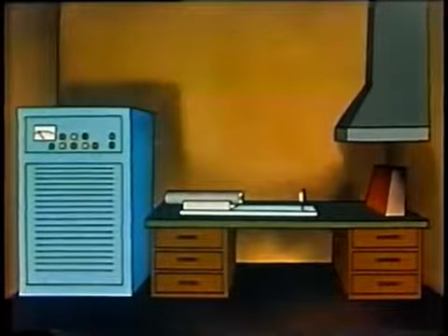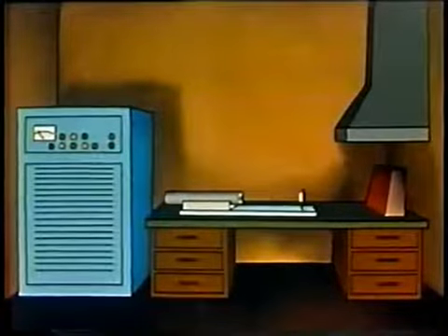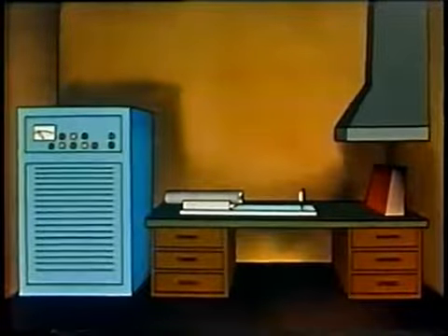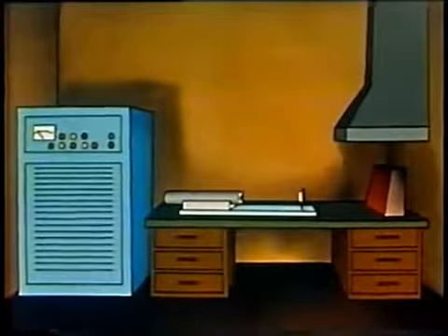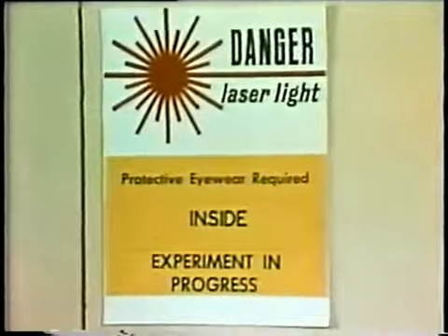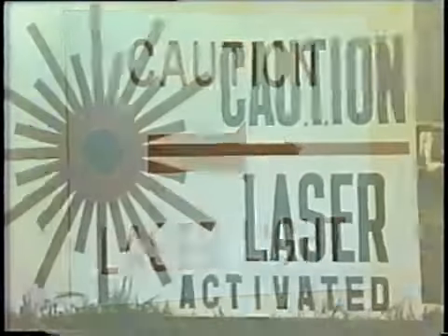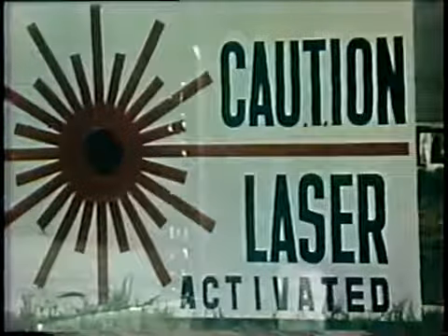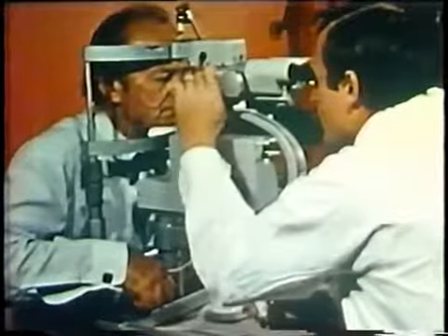Exhaust ducting should be installed over the target area to carry off toxic gases. The laser should be positioned well below normal eye level. Laser warning signs should be displayed prominently at all entry doors and near all laser operations. The laser can be a dangerous instrument. It can be harmful to those who use it, but to those who use it safely, it is a tool which can benefit mankind.